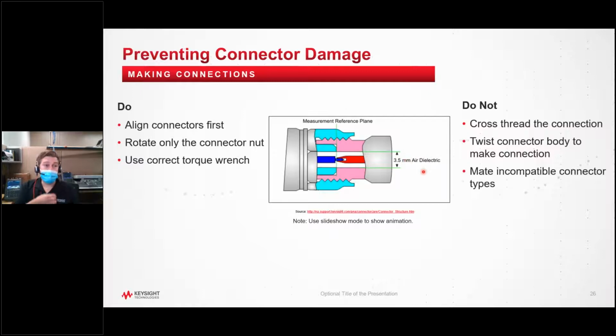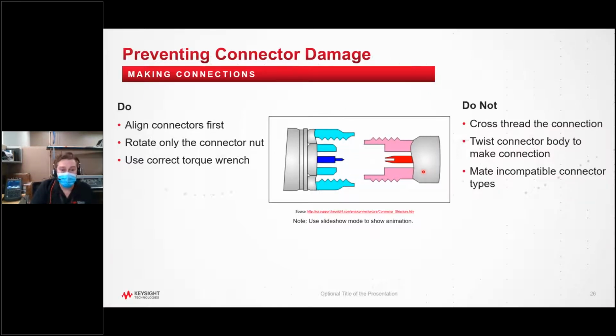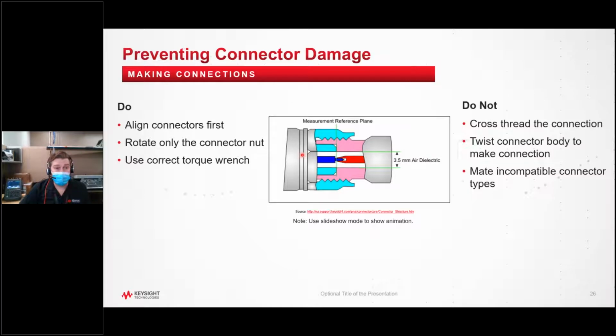There's a proper way to make these connections when you're actually putting them together, and this is important. I think it's often glossed over. You can see from this animation what it looks like in a cross section, how these things actually go together. Now, ordinarily, you would keep the female end of the connector on the right stable, and you would move the male connector into the female and hold the female connector stable, and just turn the nut on the male end of the connector. And what this does is rotate this section of the connector and allows the pin to stay stable, so you're not twisting the pin, and also you're not twisting the female end of the cable.